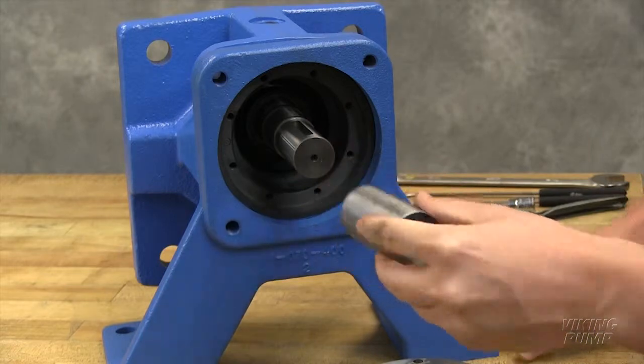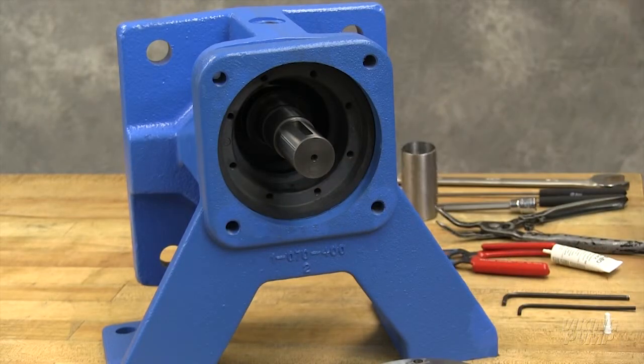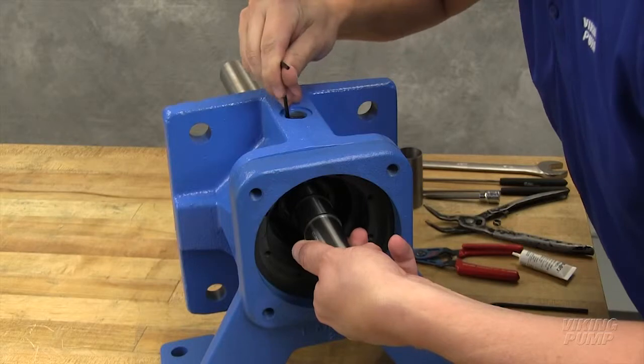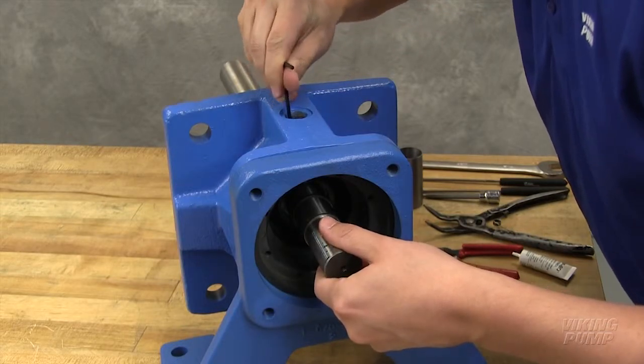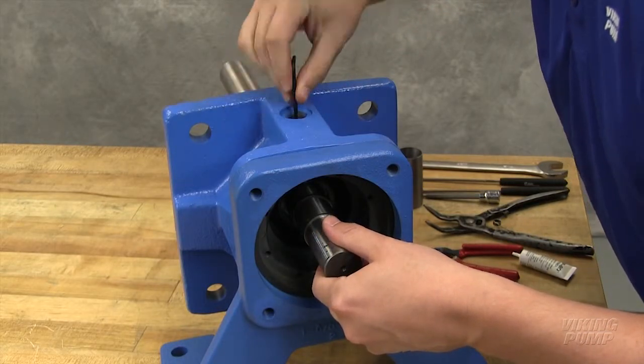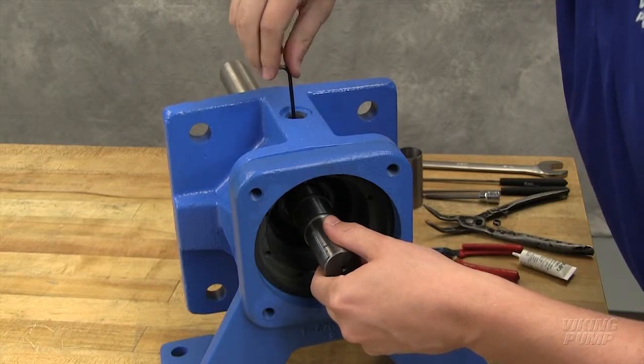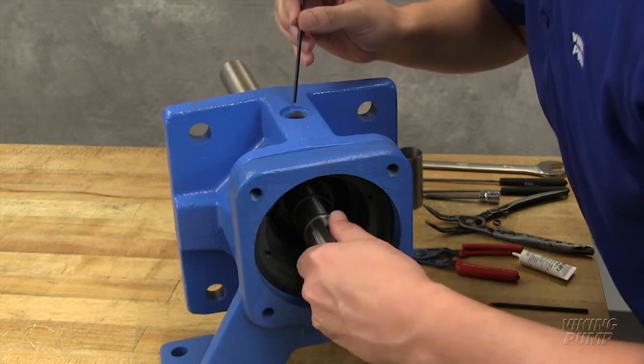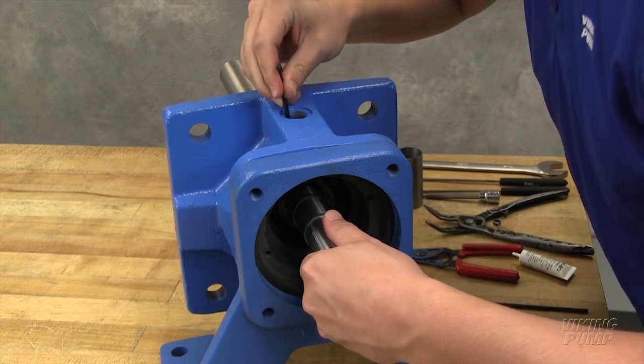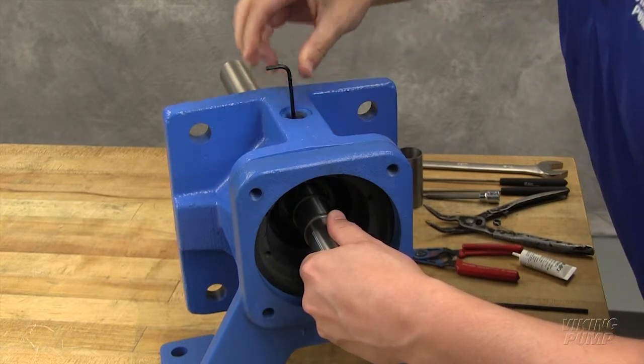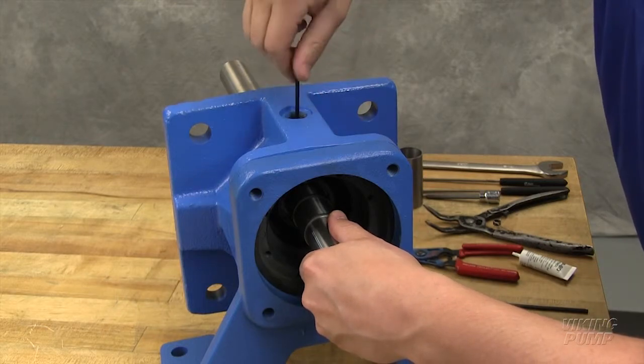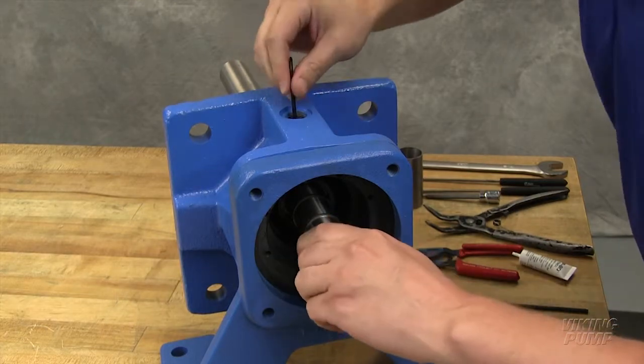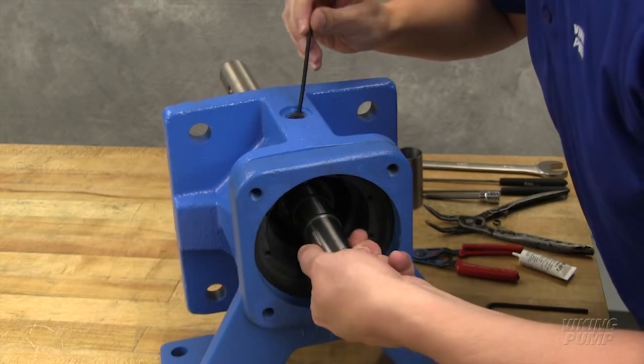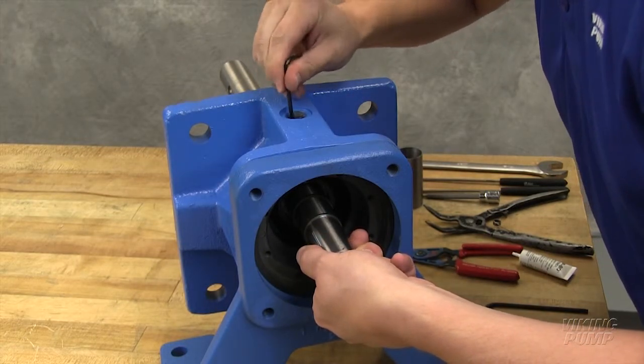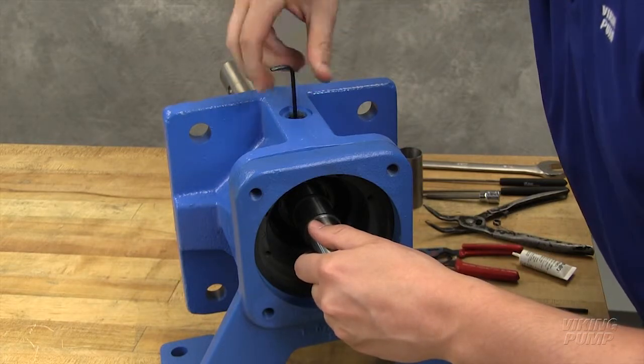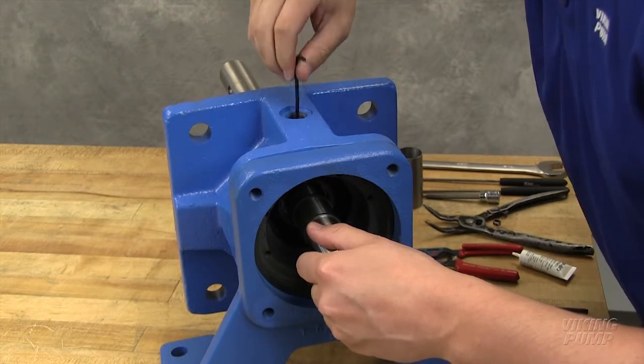Remove the installation sleeve. Make sure the seal is fully seated against the seal shim. Through the access hole in the top of the pump bracket, tighten the dog point set screw until it makes contact with the shaft, ensuring it is in the recess located in line with the keyway. Rotate the shaft 180 degrees and tighten the cup point set screw until it makes contact with the shaft. Rotate the shaft 90 degrees and tighten the set screw until it makes contact with the shaft. Rotate the shaft 180 degrees and tighten the set screw until it makes contact with the shaft.